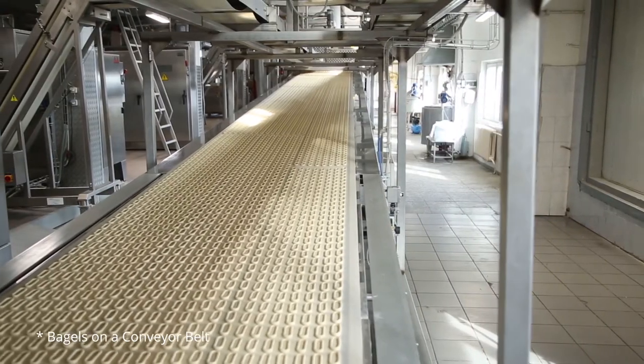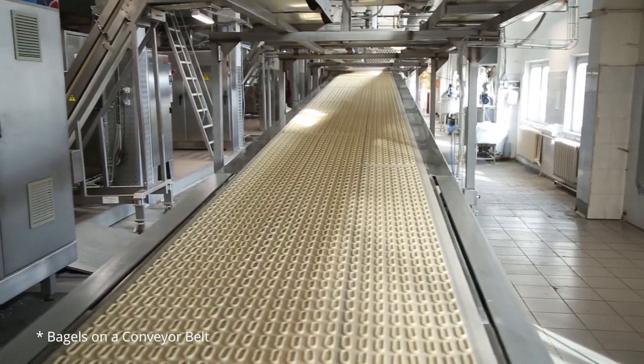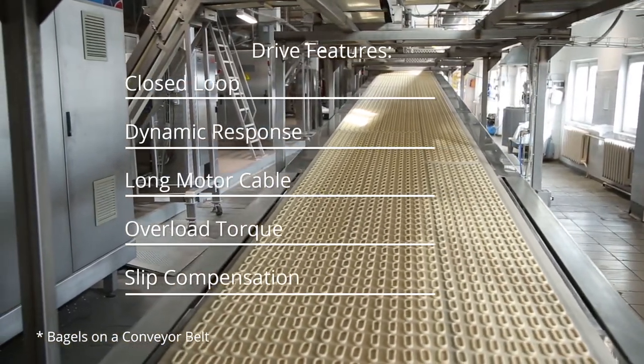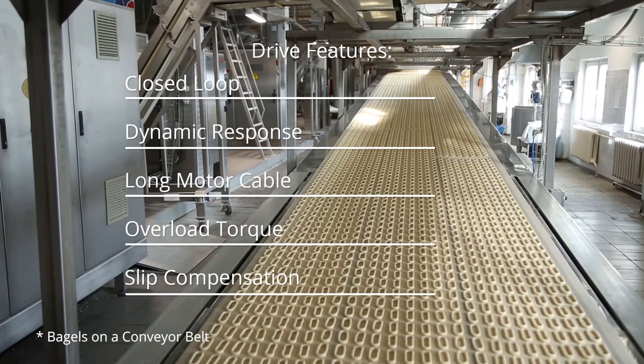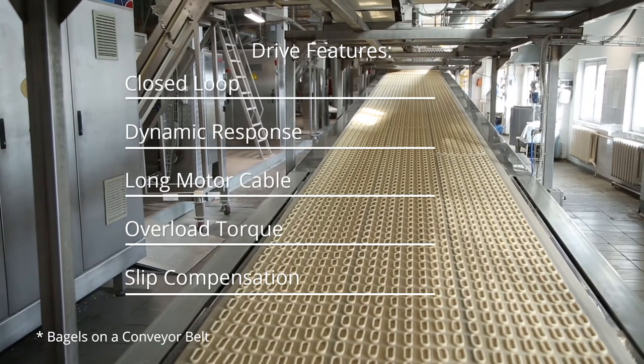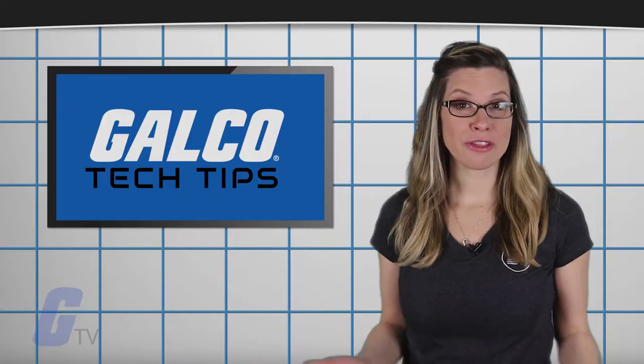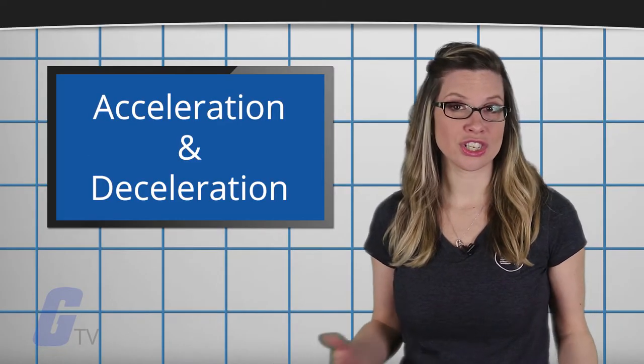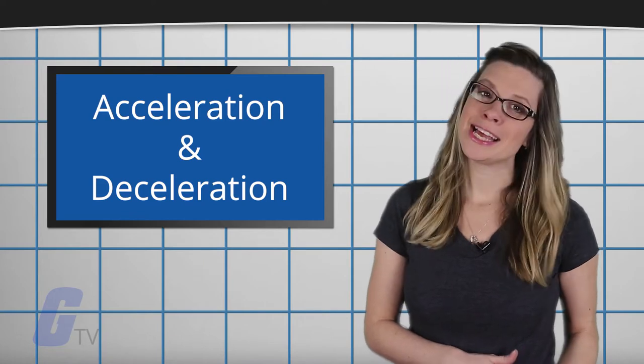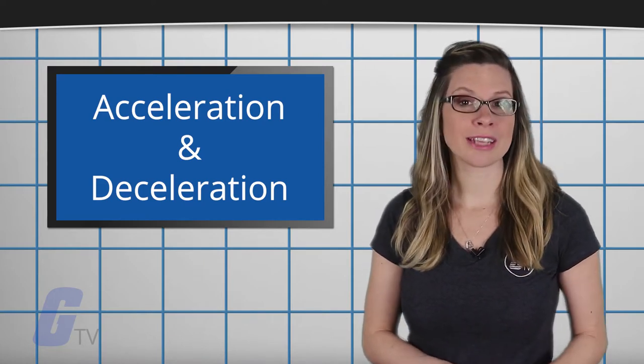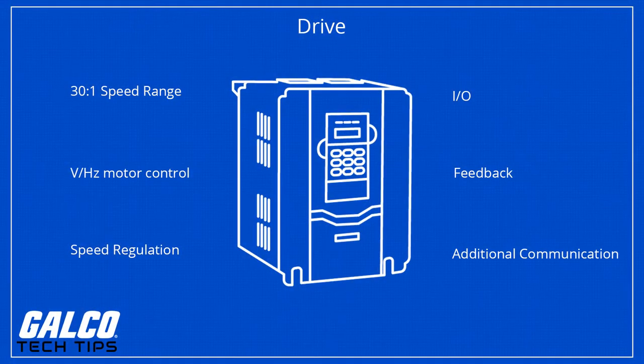For ideal belt loop operation, you will likely want your drive to feature closed loop, dynamic response, long motor cable length, overload torque, and slip compensation. Other features such as long acceleration and deceleration may also be necessary depending on your particular application. Your drive should have a 30 to 1 speed range, volts hertz motor control type, and speed regulation.